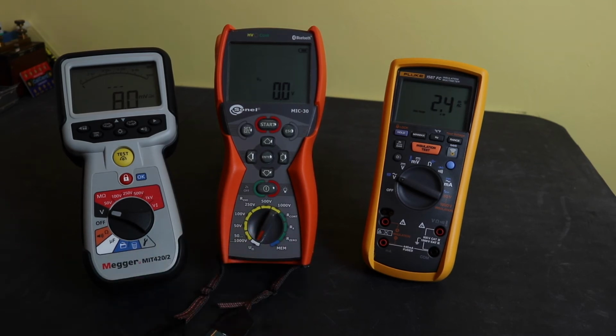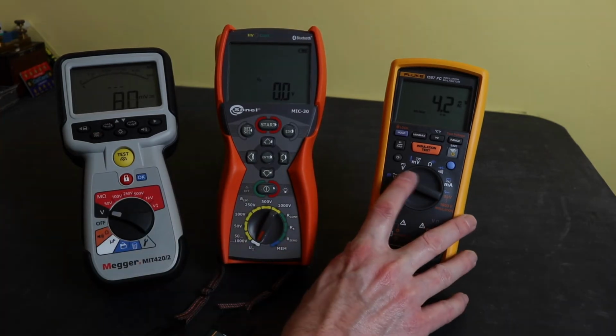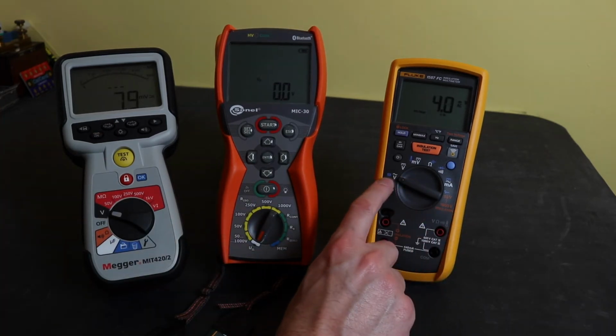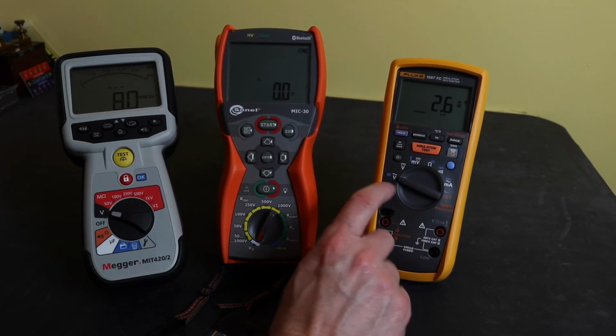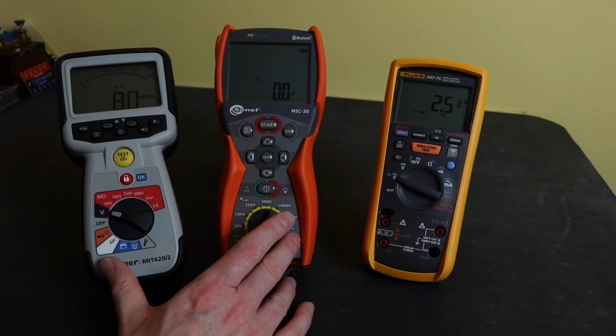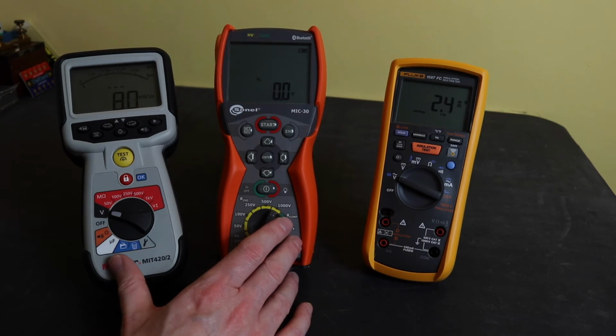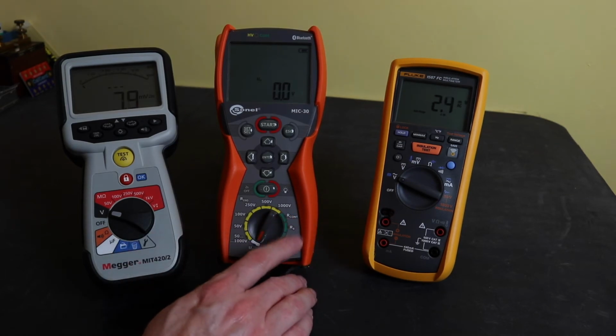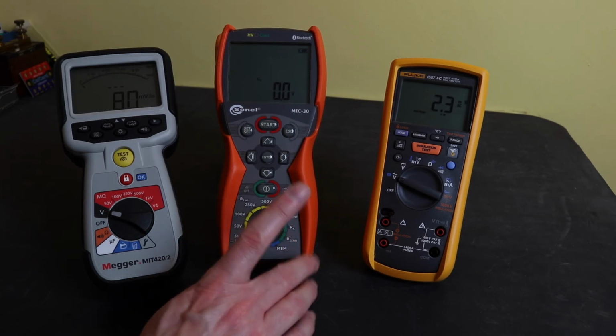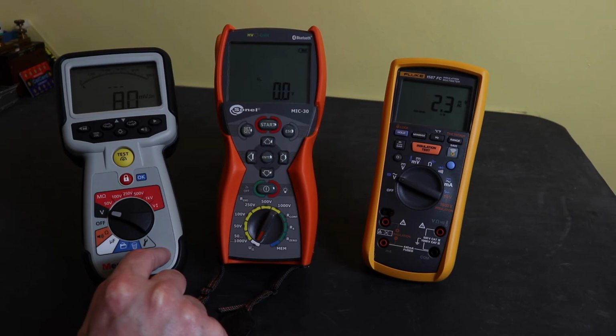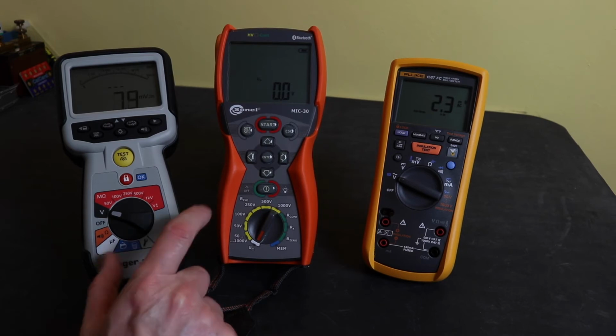With the Fluke here, AC and DC is selected off the function switch. It defaults to AC on the first position. You also have a low pass filter. The low pass filter is built into both of these instruments. This instrument is accurate only from 45 Hz to 65 Hz. Megger is 15 Hz to 400 Hz.